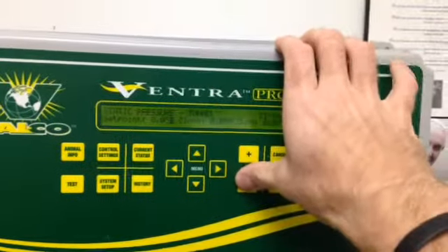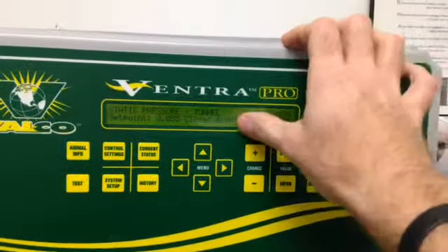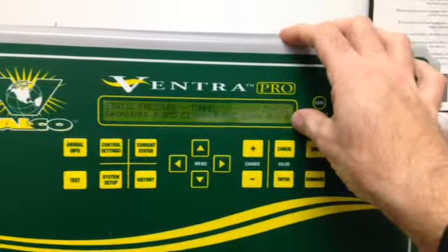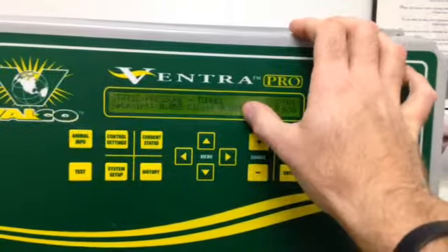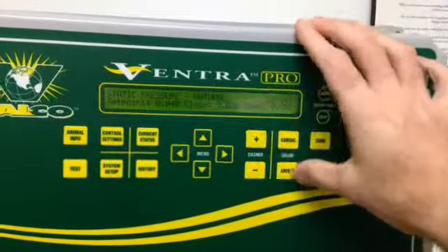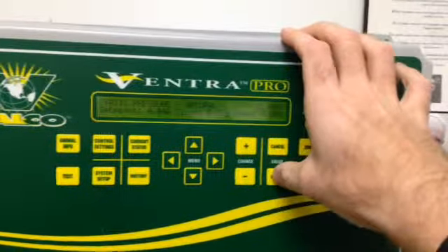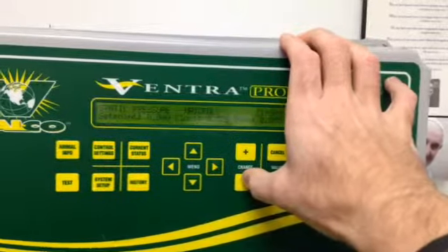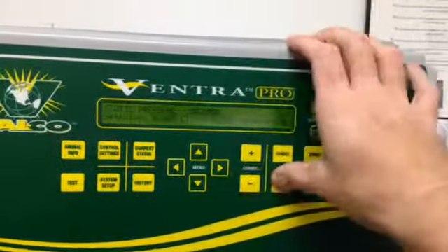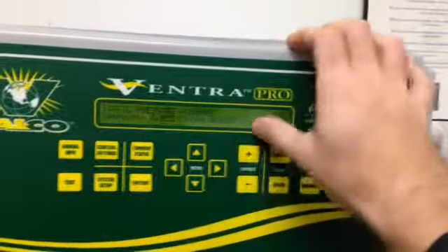You'll notice that when you're changing this set point, the close and open offsets will automatically change as well and do not seem to be user editable from the tunnel setting. If you do want to change the closing or the opening settings, go up to the natural settings, and here, independent of the set point, you can change them up or down, and you'll see those changes reflected in the tunnel setting as well.